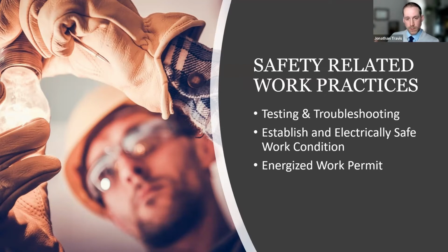The first one is that you take a voltage detector and you actually test every single phase to ground, phase to phase connection on that piece of equipment to verify that it is in fact de-energized. So you've locked it out. You go to where you're doing the work, you open the door. At this point, you're still wearing your PPE. You get out your voltage detector and you test phase to phase to ground, everything.